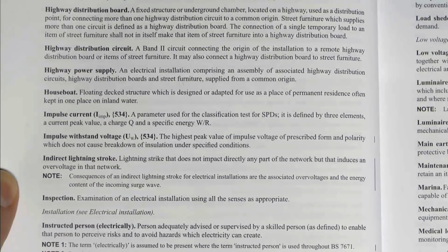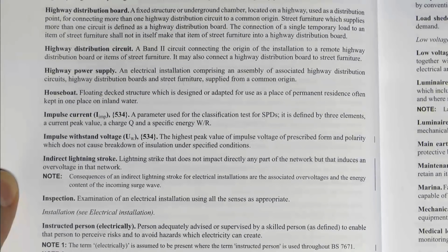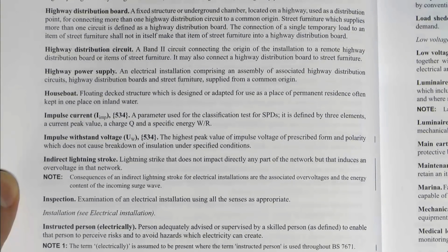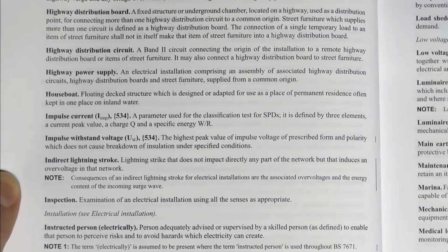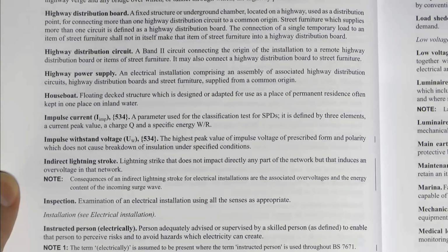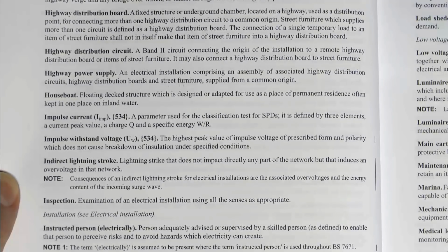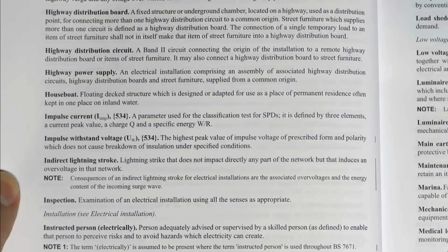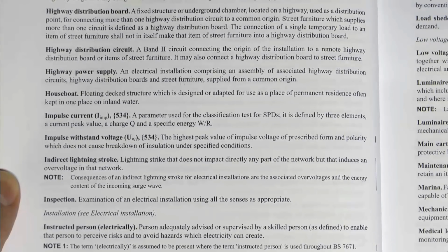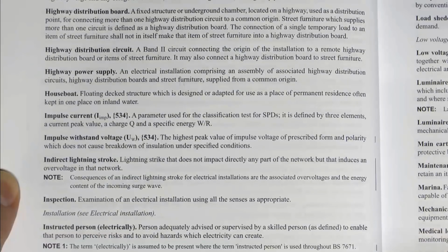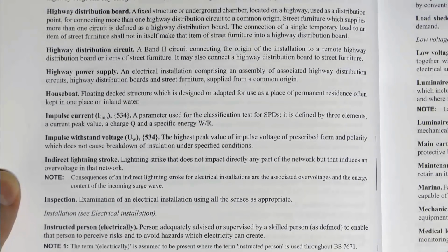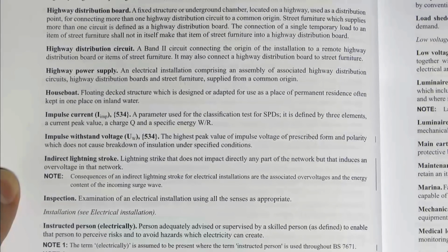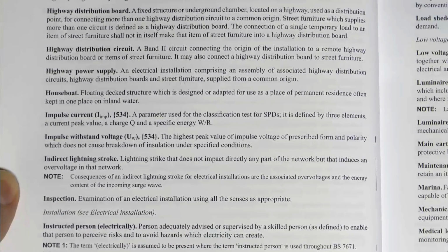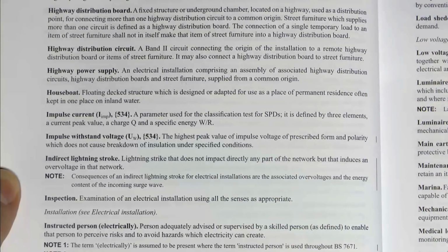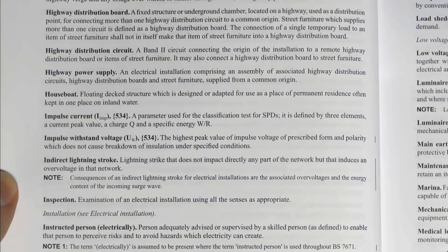Indirect lightning stroke is a lightning strike that does not impact directly any part of the network, but induces an overvoltage in that network. Consequences of an indirect lightning stroke for electrical installations are the associated overvoltages and the energy content of the incoming surge wave. A strike on, say, a transformer would be a direct one, whereas an indirect lightning stroke could be onto the ground somewhere, and that energy spreads out through the ground, which could impact cables and other nearby equipment. So just because lightning doesn't strike directly onto a piece of electrical equipment doesn't mean it can't cause damage, because all that energy has to go somewhere, spreading out through the ground and imparting onto buried cables and similar.